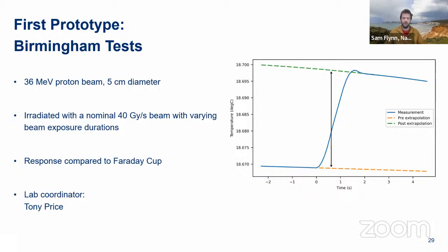I should point out though that I have kind of cheated and squashed the x-axis on this, and I'll show you that in a second. But other than that, it's the same profile that a normal calorimeter would have. You get a temperature rise. In fact, because the thermistors on this were slightly in the beam region, you get a slight bump as well, which is indicative that we're hitting something.